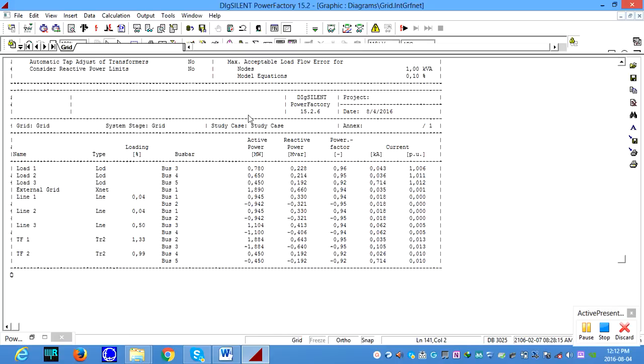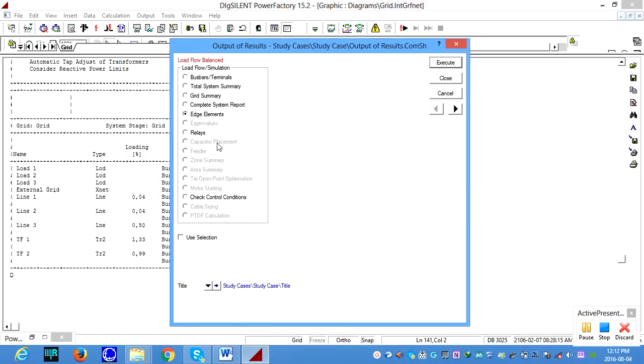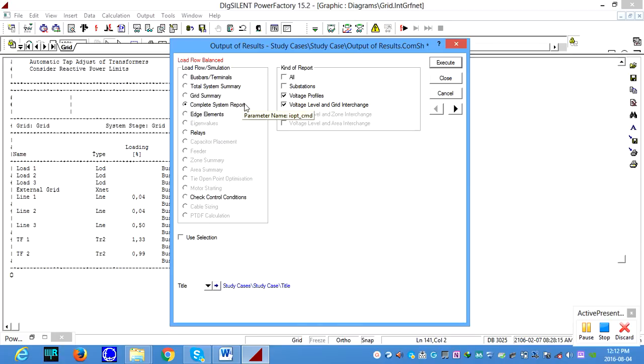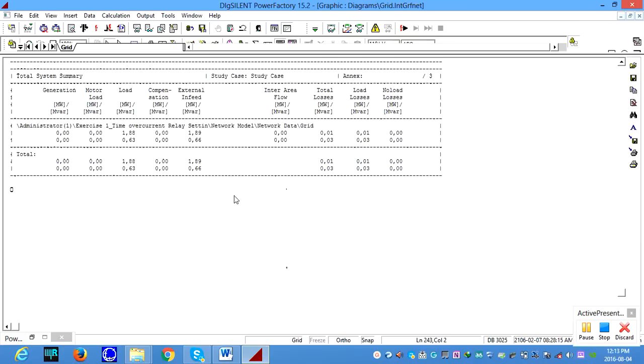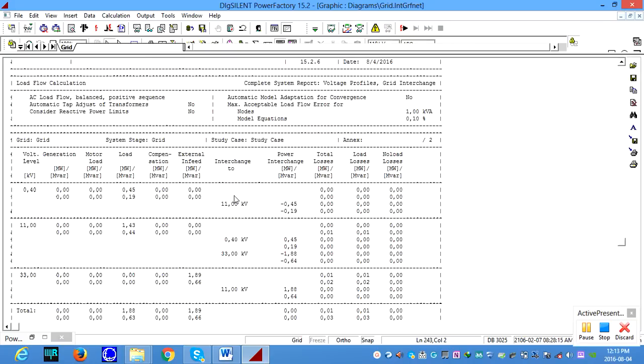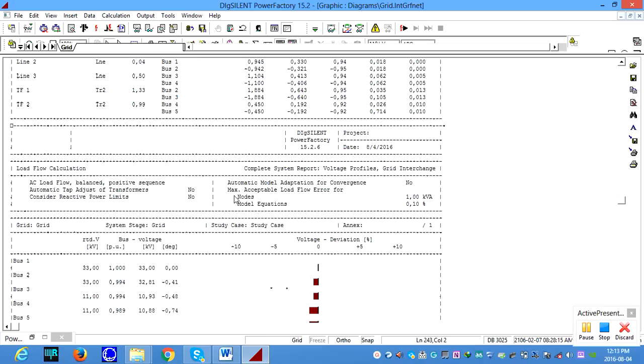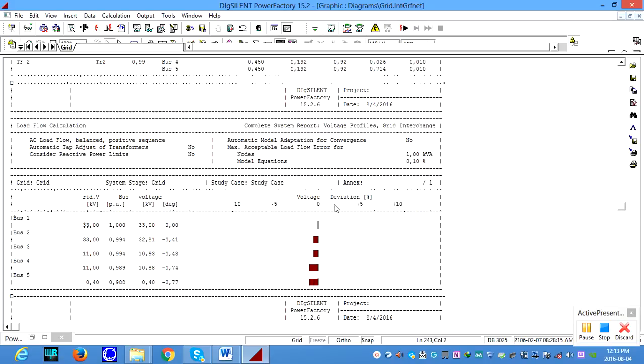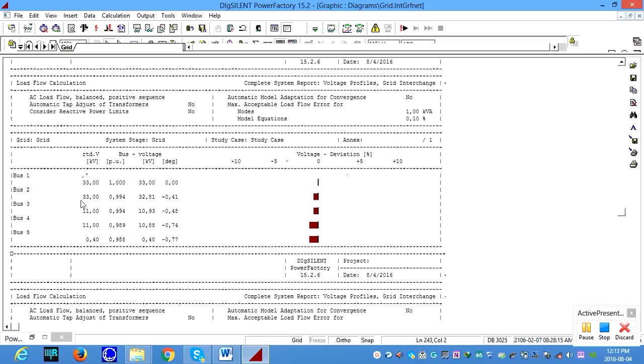element components. Okay. And we should also be able to generate a complete system report, which can give the voltage profile, voltage and grid interchange, and if you want to check all the results, or if you want a specific one, you can go ahead. So if I look for the load flow results, you can see this is a voltage profile and grid summary, and we can see these are bus voltages from 33 to 11 kV and 11 kV to 400 volt.